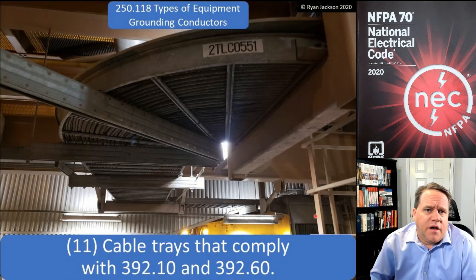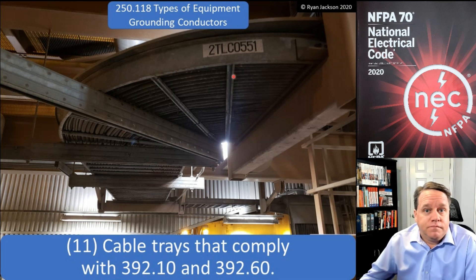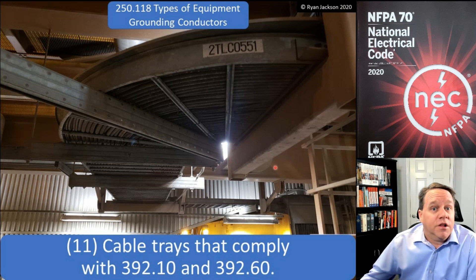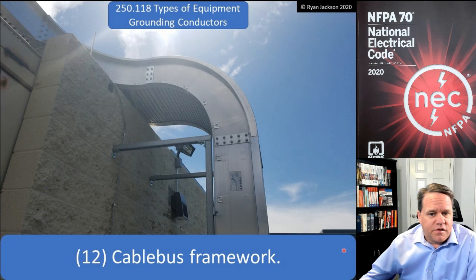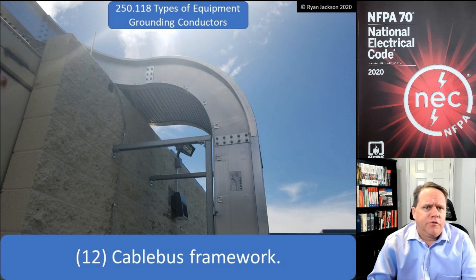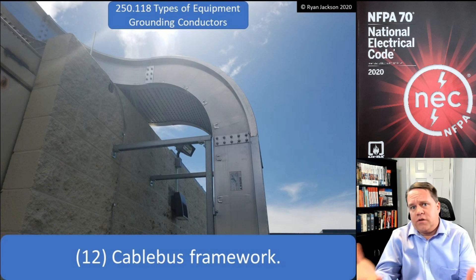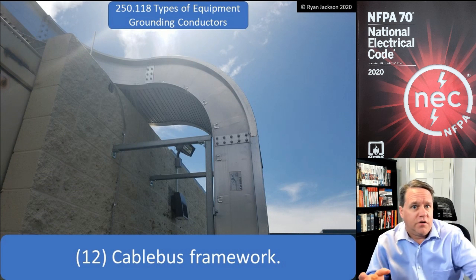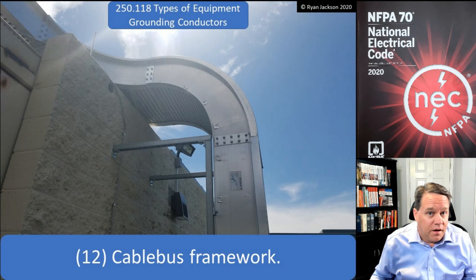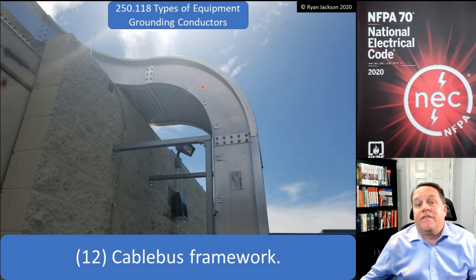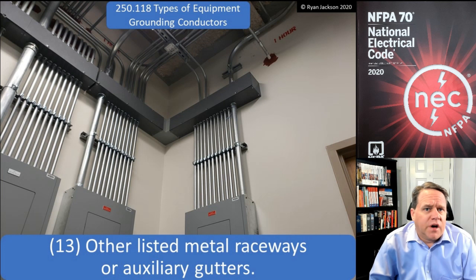You can use cable trays as your equipment grounding conductor if it complies with 392.10 and 392.60. This is a gigantic piece of metal — of course it can be used as the equipment grounding conductor; it's going to have very low impedance. The same concept applies to the framework of cable bus, which is a hybrid between busway and cable tray — you'd use this for something like a 5,000-amp feeder circuit.